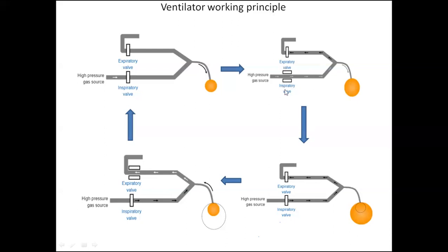So that it finally reaches the alveoli. That's the main principle in this control. The expiratory valve will be closed so that it will not take away the delivered pressure. So the total pressure delivered will stay in the alveoli. Once you deliver the pressure, say 20, what should happen to the inspiratory valve? It should close so that it keeps the pressure the same throughout inspiration.